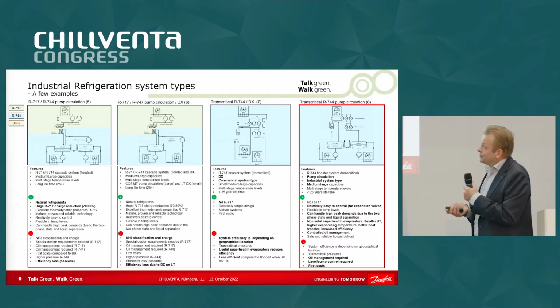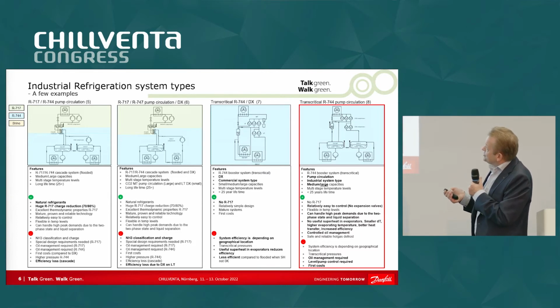You have to weld, but the only thing is the pressures here are of course higher. But the way you build is kind of the same. Another system that you can do is the same as this one, but you change the flooded LT system in direct expansion. And of course you get some efficiency loss here. This is often done if the low temperature load is low compared to the medium temperature load, and otherwise it doesn't justify the cost of building this system.